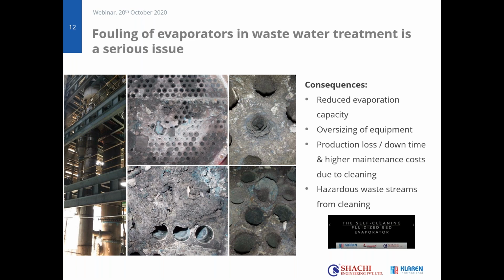At the end, if fouling becomes too severe, it will also lead to production losses, downtime, and of course, you also need to clean it. And cleaning sometimes can really be a tedious task. We recently experienced in one of the units that we were going to revamp that cleaning a 31 tube unit took almost 4 days with water jet cleaning. So that's a really incredible task.